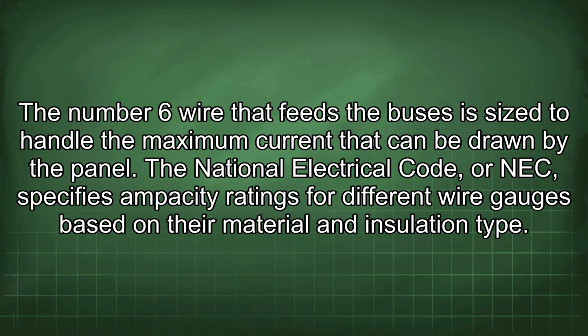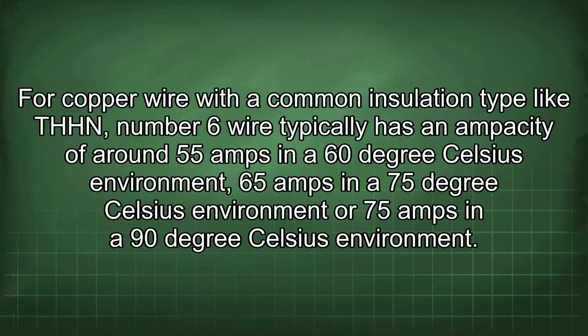The number 6 wire that feeds the buses is sized to handle the maximum current that can be drawn by the panel. The National Electrical Code, or NEC, specifies ampacity ratings for different wire gauges based on their material and insulation type. For copper wire with a common insulation type like THHN, number 6 wire typically has an ampacity of around 55 amps in a 60°C environment, 65 amps in a 75°C environment, or 75 amps in a 90°C environment.